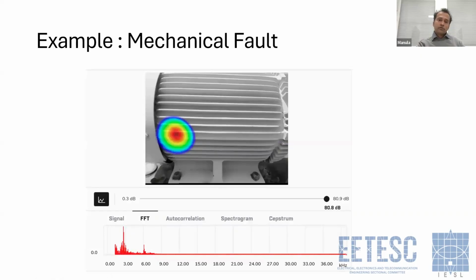When it comes to mechanical faults, we can again upload this file and open it with this tool and have a look. Some engineers want to look at the frequency components of this sound wave. For example, in this case, we have a 3 kilohertz frequency as well as a harmonic at 6 kilohertz. These engineers can then relate these frequencies to the characteristic frequencies of the element. For example, in this case, this is an induction motor. Induction motors might generate rotor bar defects, which might have specific frequencies. Engineers can correlate these frequencies, check what kind of fault is there, and predict these things.